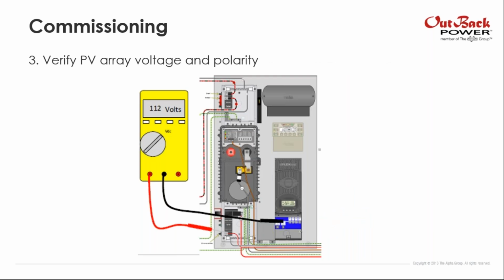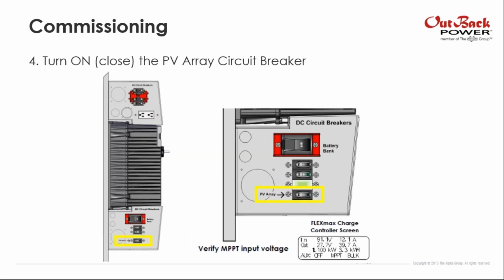Three. You have to verify the PV array voltage and polarity too. You will do this checking with your multimeter from the PV array breaker input and the PV negative terminal in the FlexMax. Then turn on the PV array circuit breaker. When you turn on that breaker, you will see in the FlexMax charge controller the voltage and current that you are generating at that moment. You can check it on this screen. You will see voltage, you will see current, you will see instant power, and it will start to count the energy, I mean kilowatt hours.